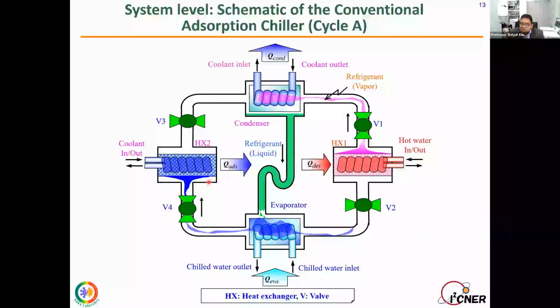So one bed is in adsorption mode, the other is in desorption mode, and then vapor goes through valve 1 to the condenser. The condenser is also a water-cooled condenser. We cool down this vapor, the phase changes in the condenser, and the liquefied water comes back to the evaporator. The science here is that when water evaporates, it creates a temperature difference. For example, the water inlet is about 12 degrees and the outlet would be about 7 degrees. Then the temperature difference can be used as cooling energy. If you have a higher water inlet flow rate, you have more cooling energy. Of course, it depends on the size of the system. So we can work on this.